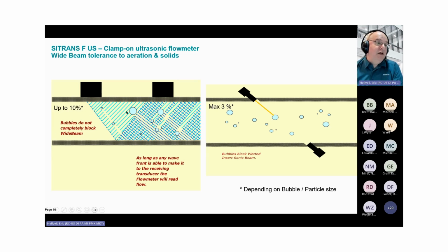So you can have 10% particulate or air bubbles disrupting the sound here, but in a direct shot on a wetted set of transducers, one air bubble can shut you down. That was the message here. So we use a very wide footprint and we use a direct reflect.